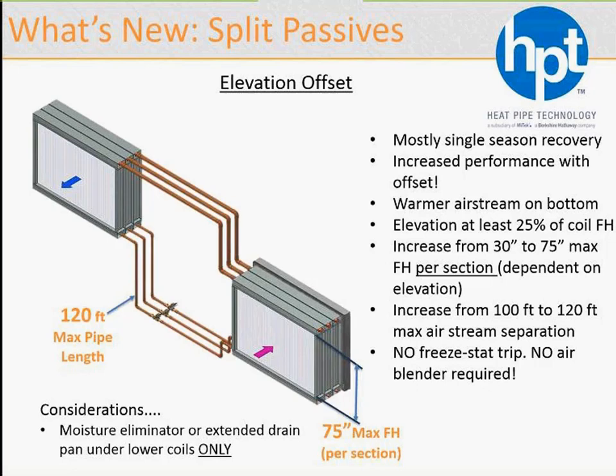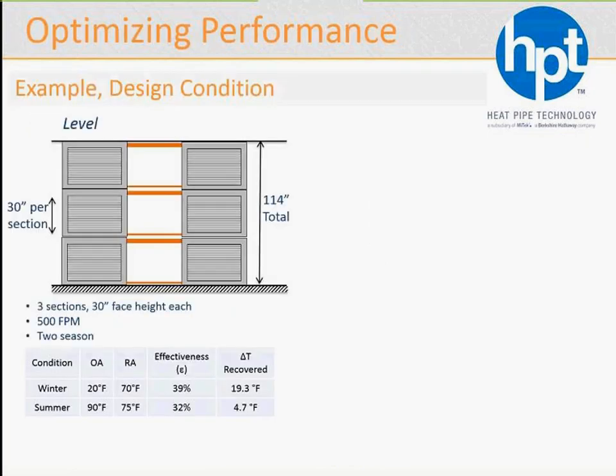Okay, let's take a look at performance. What we're seeing here is level performance, because at this level the maximum section height is 30 inches. So for this particular example, we will need 3 sections stacked. And what you're looking at are those orange pipes that go between the supply and exhaust: the vapor line up top, the liquid line on the bottom, and so on.